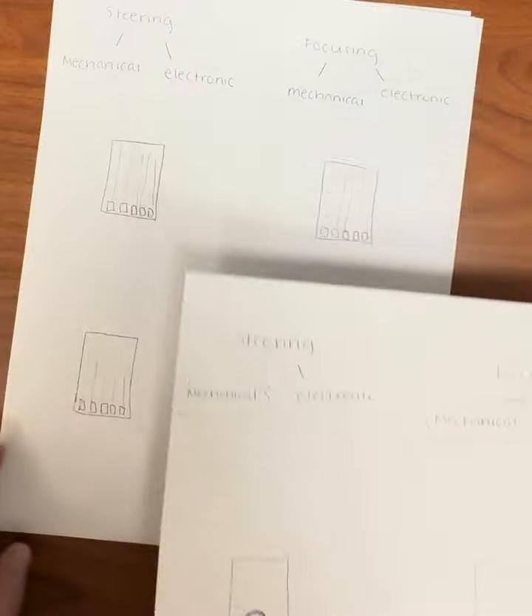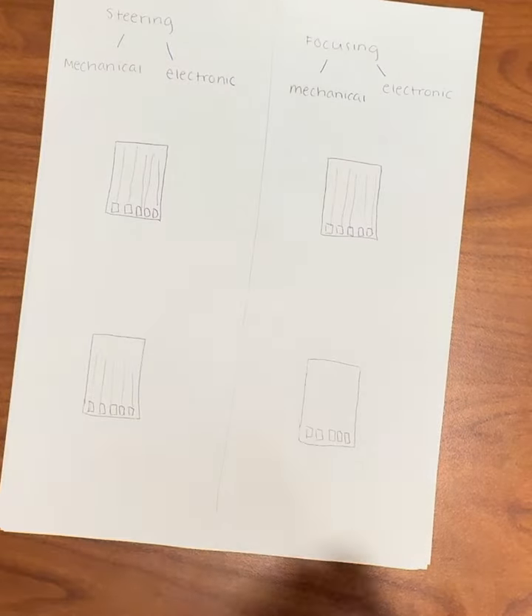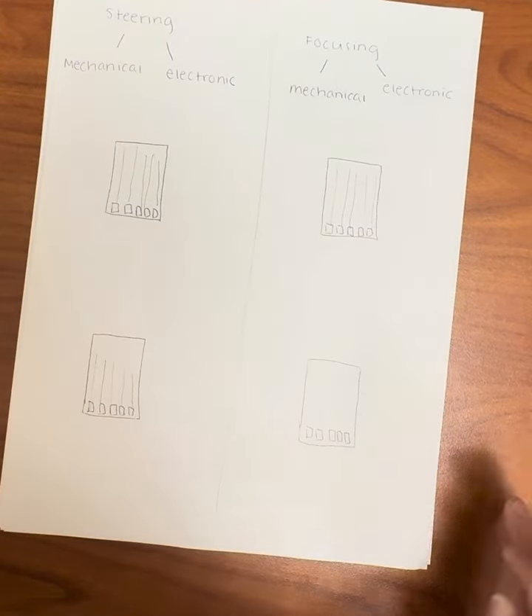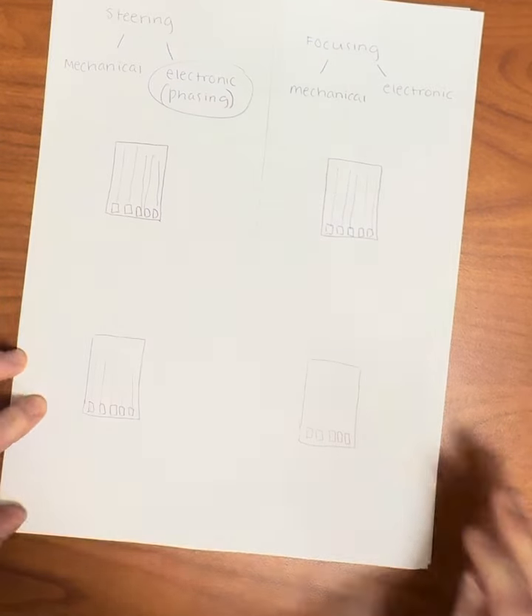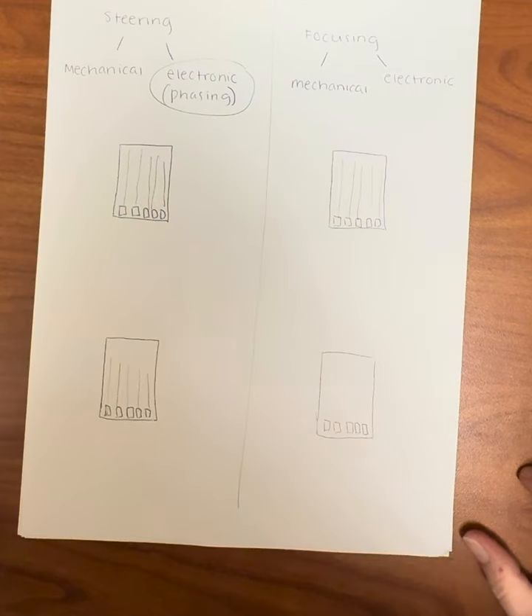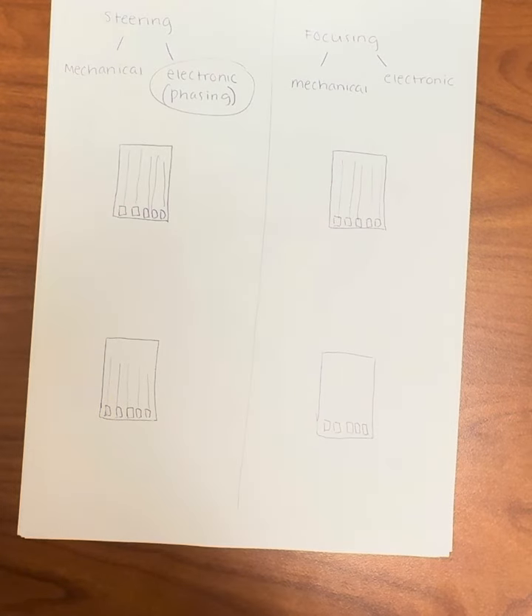These days our transducers are doing these same things but electronically. So electronic steering is done through a process called phasing. So that's where the phasing comes in. And all phasing means is that it is a delay in sending signals to certain elements. We do it in phases to get the desired result that we want.